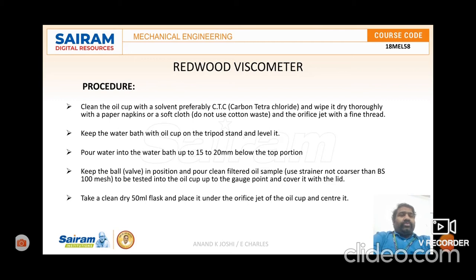First, we have to clean the oil cup with a solvent, preferably carbon tetrachloride, to ensure that there are no dirty particles on the flask or cup.